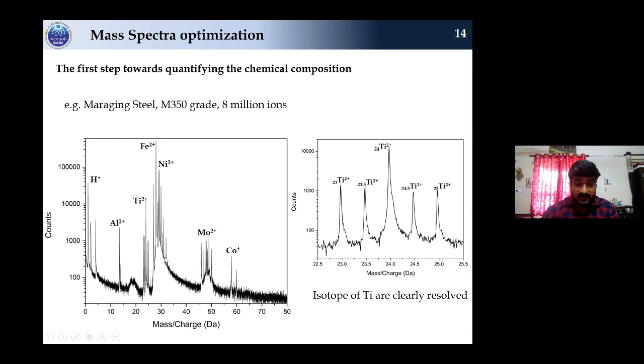If you remember, I talked about thermal tails in my previous slide. Here in this mass spectrum, one can clearly see an exponentially decaying tail. One should not have this. In this case, the magnitude of this tail is very small, but sometimes it could be large, and the moly and cobalt peaks will merge into the noise. This thermal tail happened because of the laser energy used.